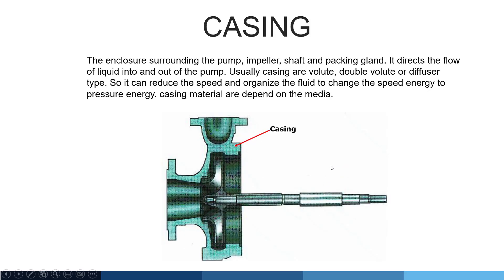The casing is the enclosure surrounding the pump impeller, shaft, and packing. It directs the flow of liquid into and out of the pump. Usually casings are volute, double volute, or diffuser type, which reduces the speed and converts the speed energy to pressure energy. Casing material depends on the media being pumped. You can see the casing in this picture.